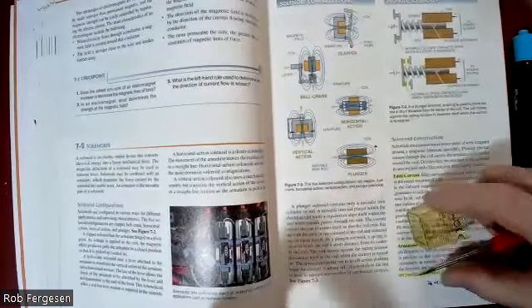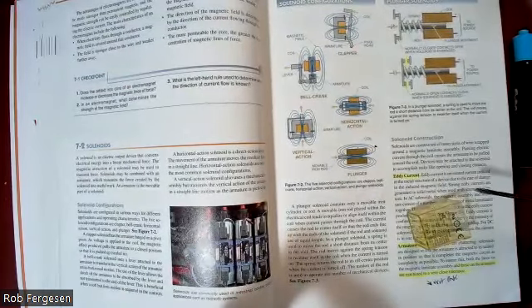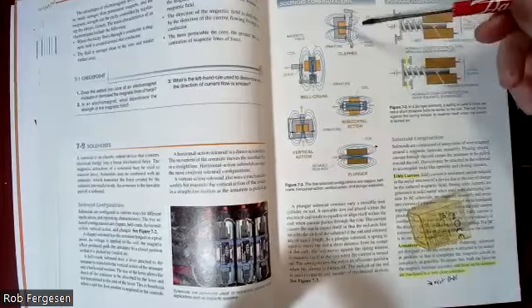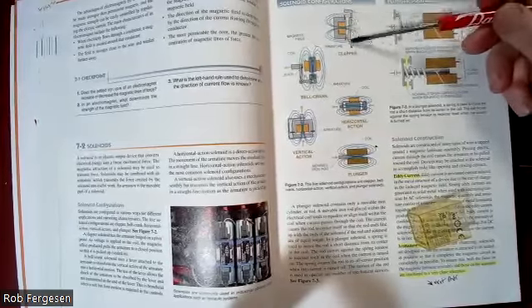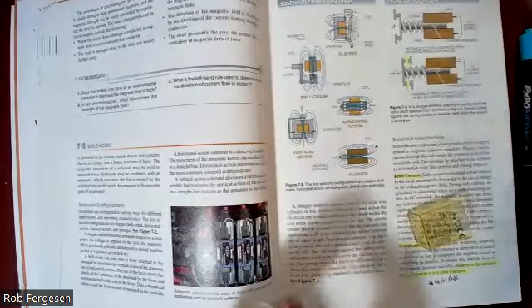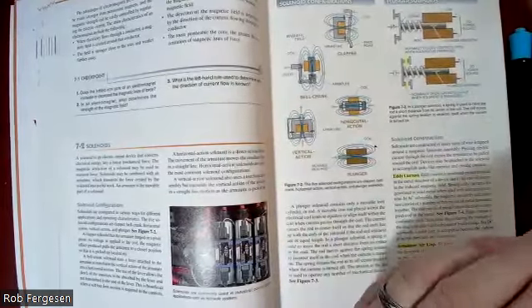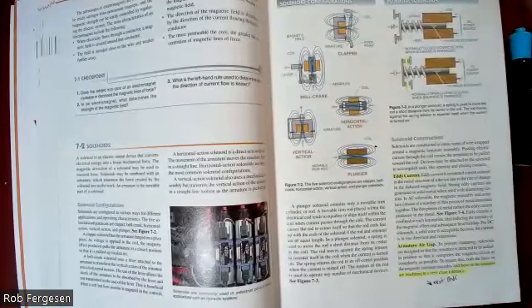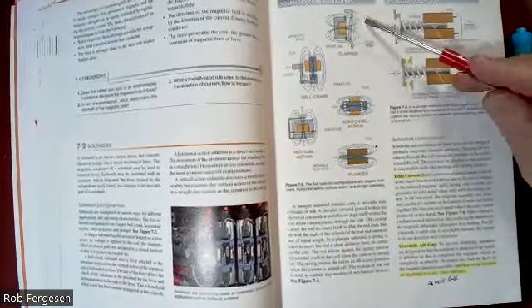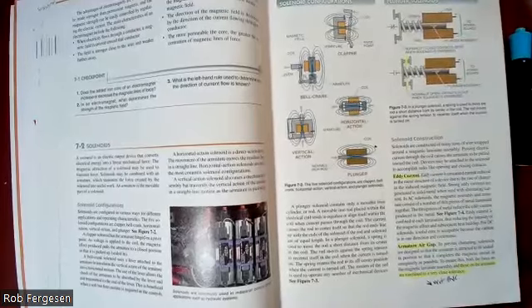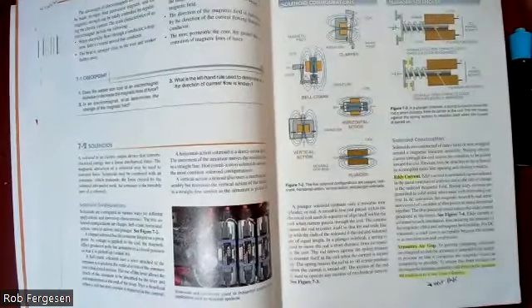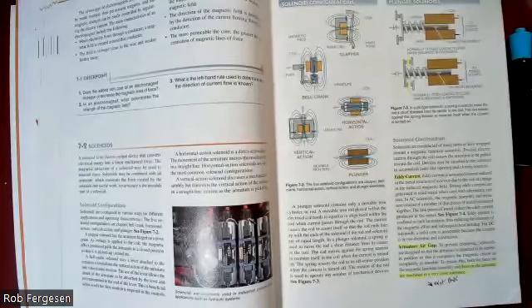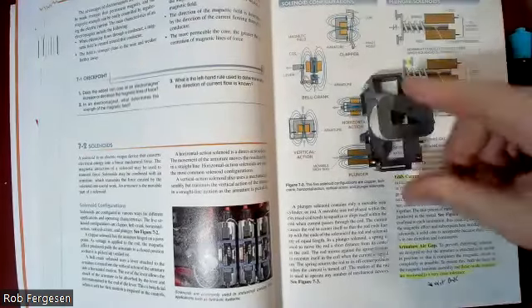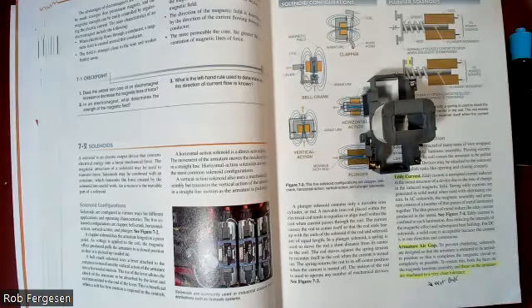All right, so that's a pretty typical kind of orientation. That's a clapper orientation, where you've got a plate that gets sucked up against a coil and then causes that contact to be made. So these are all different configurations. The actual configuration doesn't matter. Let me just divert a little from the book. What matters is: is the coil replaceable on the solenoid that's broken?